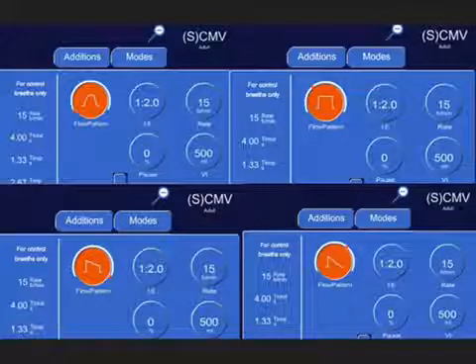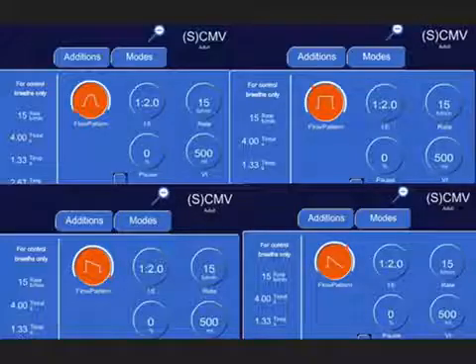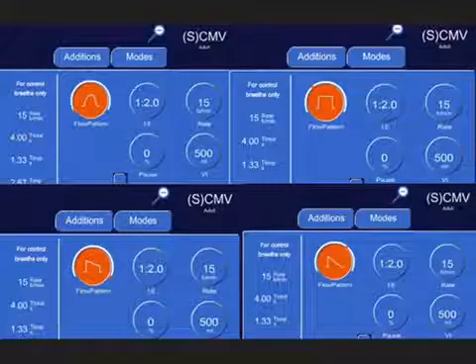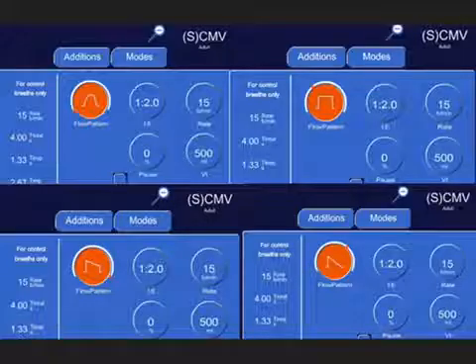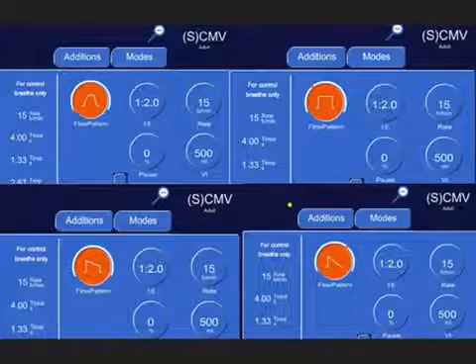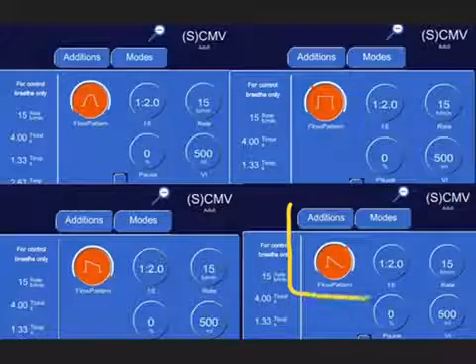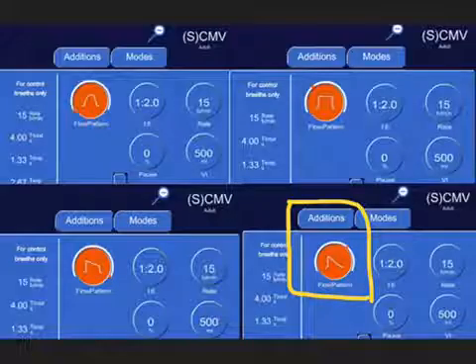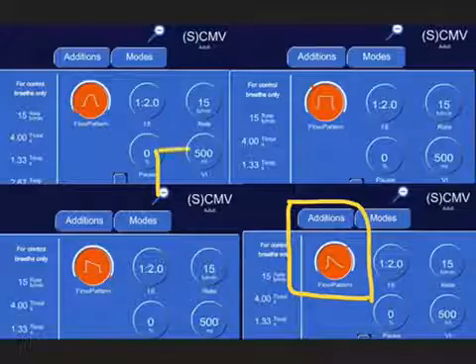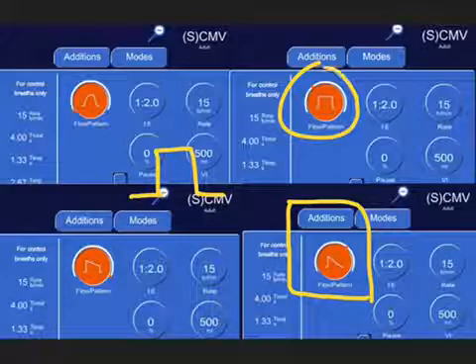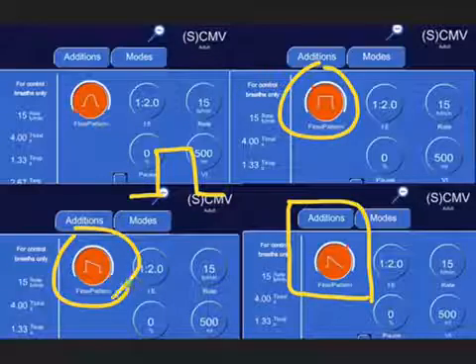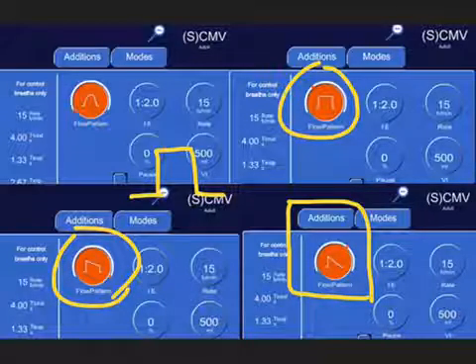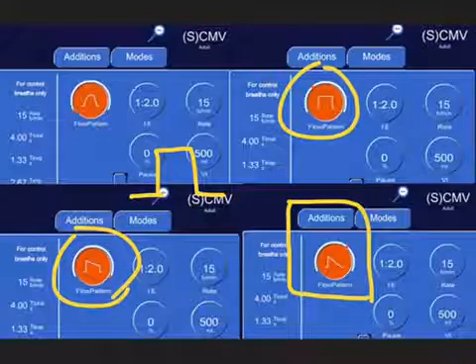So, if you are using volume control ventilation, you want to use a fully decelerating flow pattern or the tables math do not line up. So here's an example of a ventilator with four different flow patterns. And as you can see in the lower right hand corner, this is the flow pattern you want fully decelerating. Not all ventilators allow you to set a full decelerating flow pattern. Most use the constant flow or the square pattern as seen here or a partial decelerating. This is the most important thing: if you are using volume control and you want to use these tables, it has to be fully decelerating.